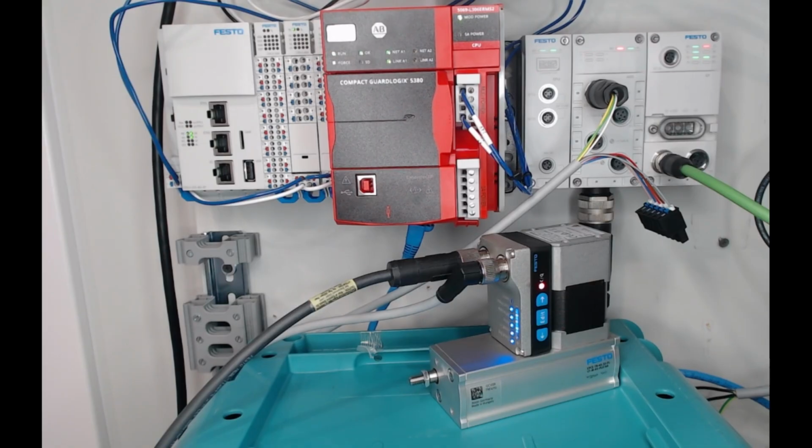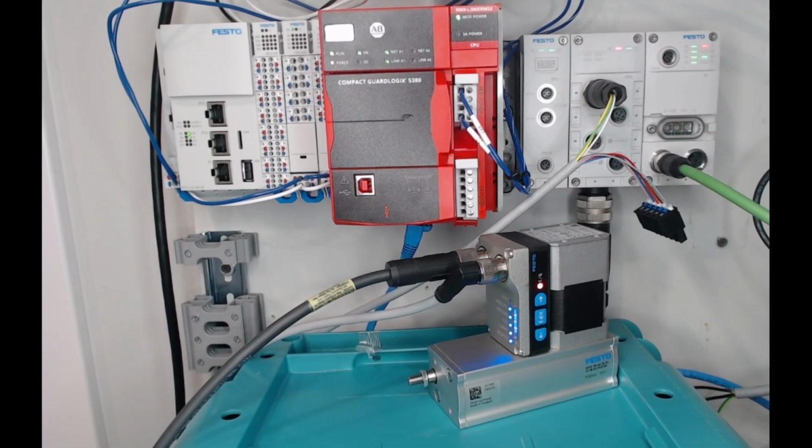In this video, we're going to be taking a look at how to implement the SMS Startup AOI. This is for our Simplified Motion Series, or SMS actuators. The goal of this AOI is to overcome the initial startup sequence of these SMS motors.